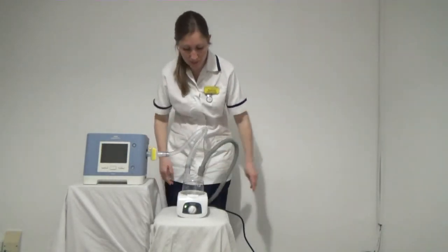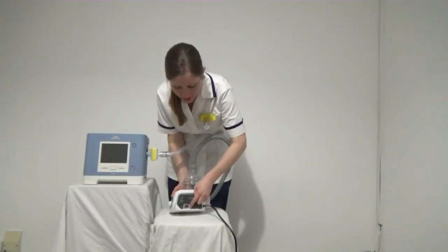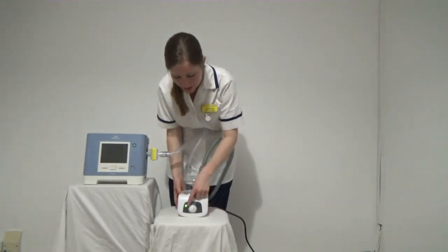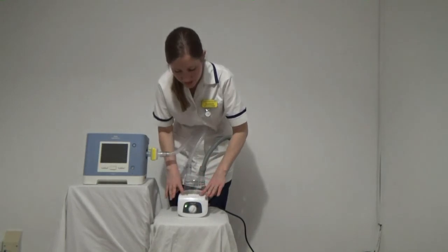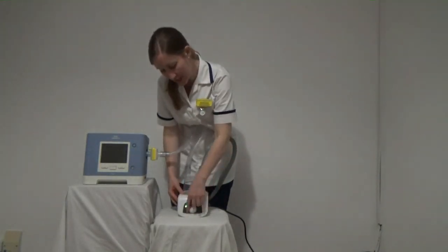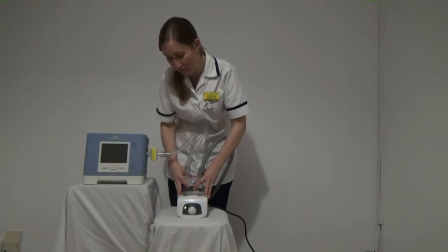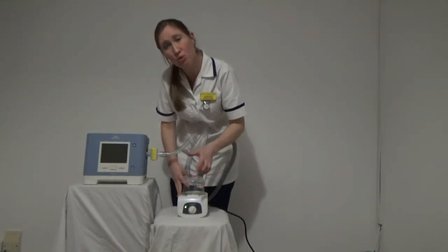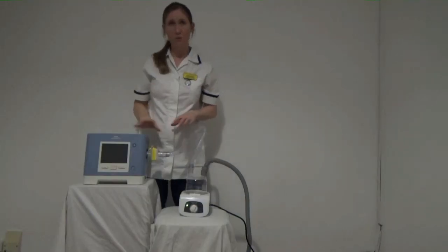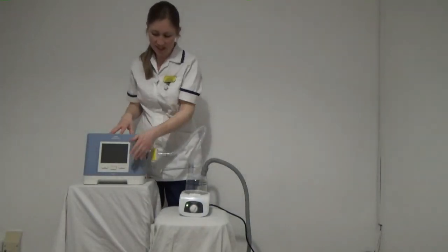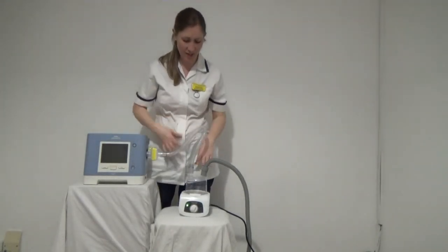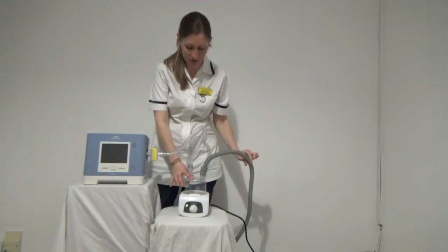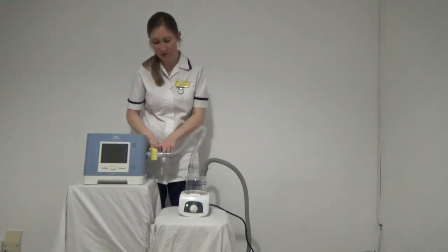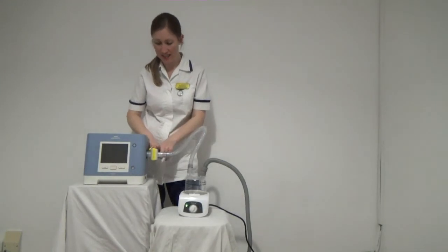Now, with the inspired version, there is an on and off button at the side, so do make sure it's turned on, and when it is on, this will glow green. For this model, we recommend that you only have the humidification set at number 1, as this can over-humidify otherwise. With the Fisher & Paykel version, you have more freedom to turn up and down as required. Once your humidification is set up, turn on your ventilator as usual, and air will blow out of the ventilator over this pool of warm water and into the hose connected to the patient. If you are advised to use yellow filters, these do need changing daily.